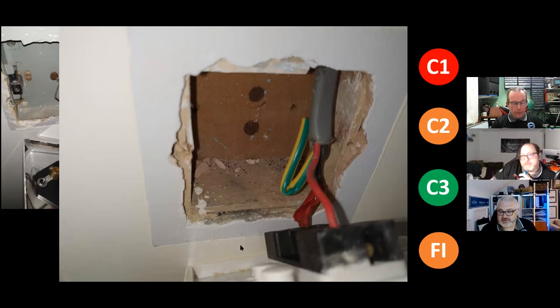What have we got on this? We've got mainly C3, a couple of C2s. Yeah, I think that's reasonable. There's nothing immediately dangerous here, and it's not really anything that's going to become dangerous. It's in a brick and plaster wall, isn't it? So it's not going to spread a fire. Yeah. No, the only thing you need to be careful of is that hole where the cable comes down. But relatively, the volume of material that could burn is very unlikely to produce a level of heat where you could actually get a transference which could heat another combustible surface to the point where it would catch fire, i.e. a joist above it. So I wouldn't put that as a C2, although Mr. Watts will tell me otherwise.